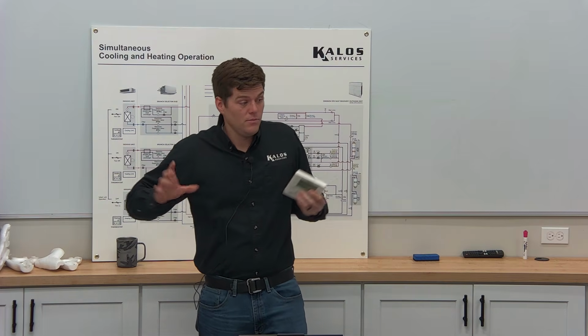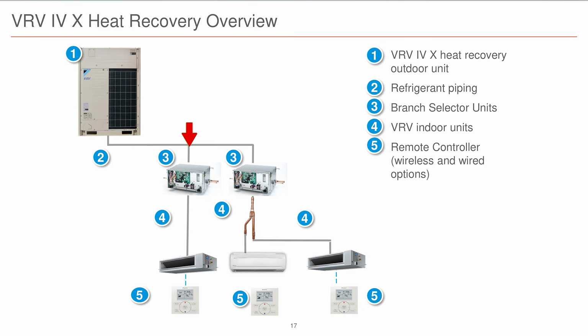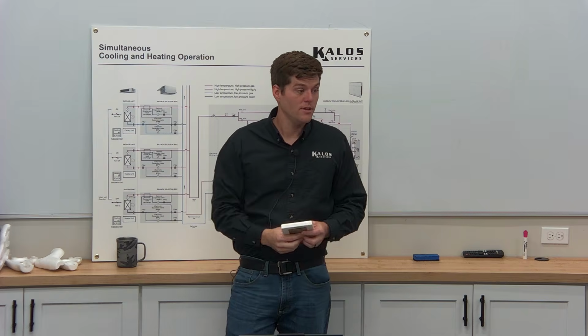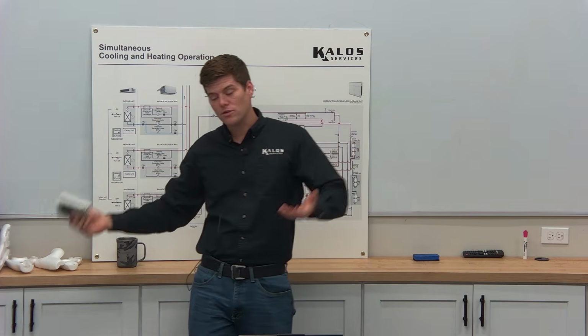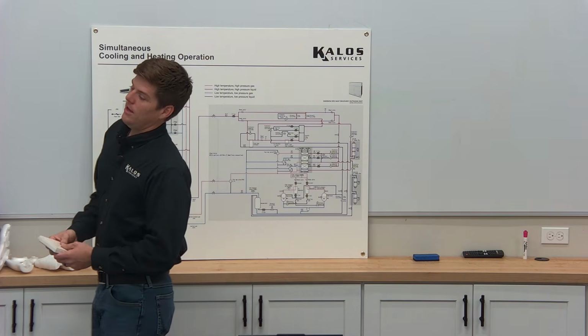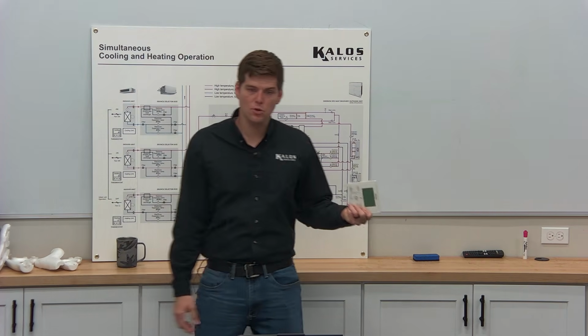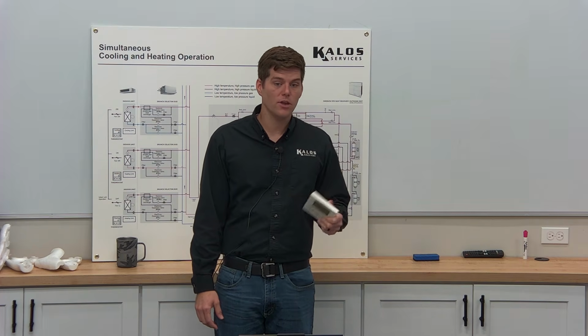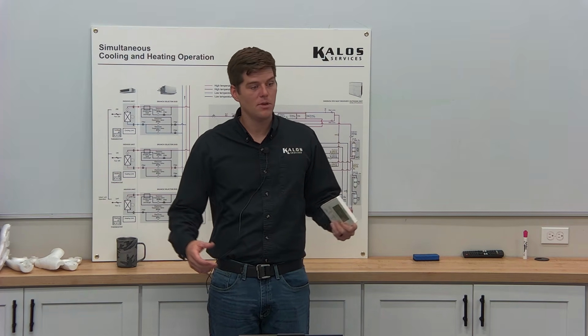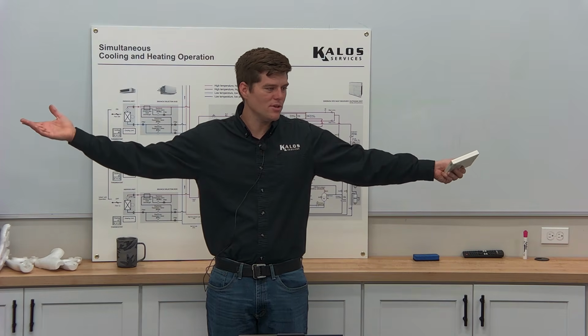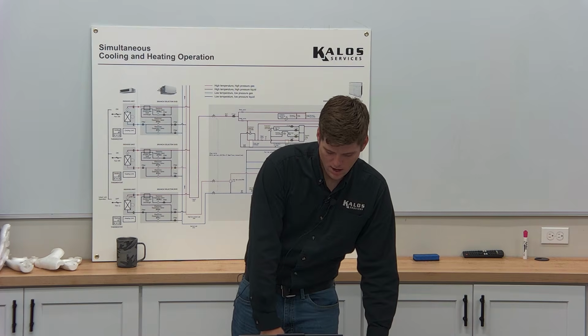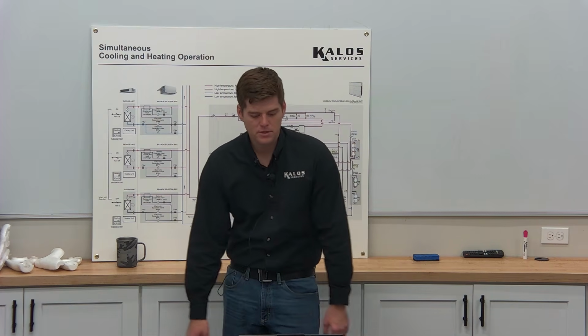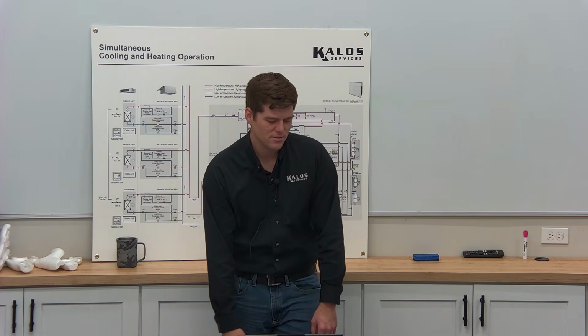So, you got one unit, 1-to-1, right? Does whatever it wants to. Then you got the 2 units that are on one box. It's married to another. So if you go to a service call, you look at a system, and you can't make changes, it only goes into cooling, it won't go into heating, you have to look for the other unit that might be on the same system. It might be a giant apartment, and there's 2 units, and there's a controller somewhere else in the back bedroom. All right, there's other rules that we've talked about. That turbulence.